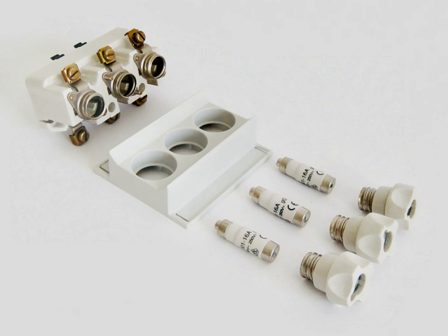IEC 60269 unifies the electrical characteristics of fuses that are dimensionally interchangeable with fuses built to earlier British, German, French or Italian standards. The standard identifies application categories which classify the time current characteristic of each type of fuse. The application category is a two-digit code.